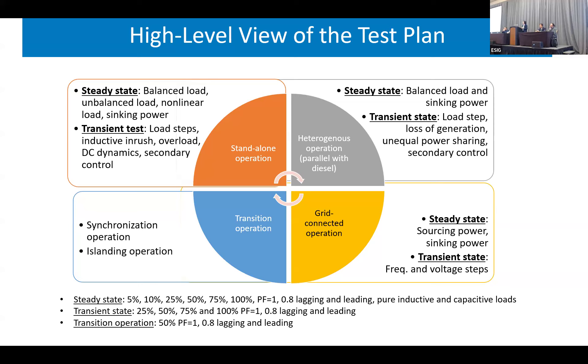We also did transition operation — the islanding mode application. We start from islanding mode, synchronize to the grid, then go back to islanding mode again. These are the high-level views of the tests we have done — very comprehensive, standard, and strict. We also have standard performance metrics for evaluating each inverter. As of today, we have completed all unit testing.